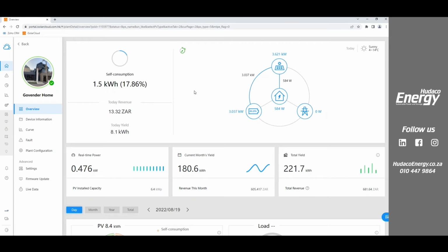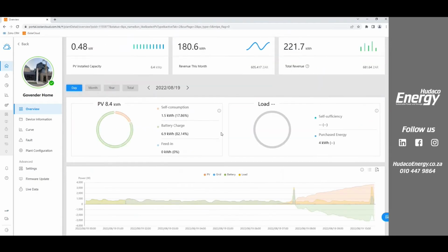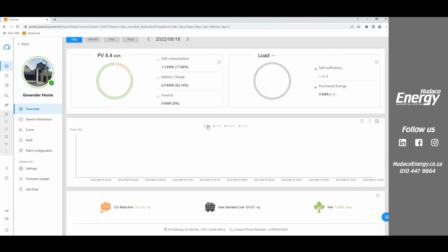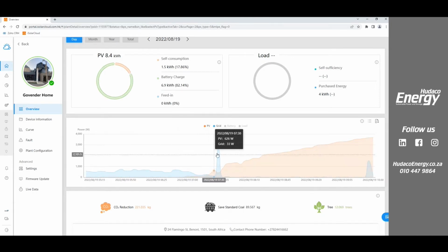So here we can see we're getting 3.6 kilowatts out of the PV panels. The home is using 588 watts. 3 kilowatts is going to batteries. They're pulling nothing from grid. What this looks like is, here we go. If I zoom in here a little bit on the daily yield, let's turn everything off and come back on. So if we turn on the PV, we can see they started producing 655 this morning. It's been going up. We look at their grid use. They ran on grid last night. This morning there was a little bump, 3.5 kilowatts, probably a geyser.